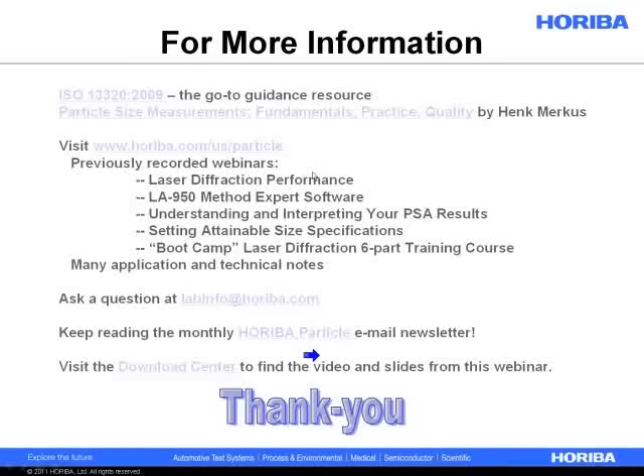Gregory asks where he can find more information about the R parameter — we have a technical note on our website that discusses the R parameter and the chi-square value, in the Download Center under Technical Notes. Ryan asks: when he uses ultrasonics, sometimes the transmittance drops out of the green zone — what effect does this have on the final measurements? This is actually very typical. What you're doing with the ultrasonic is improving dispersion — taking large agglomerates that may look like 5 microns in diameter and dispersing them into 1-micron primary particles, so the total surface area increases and more light gets scattered.